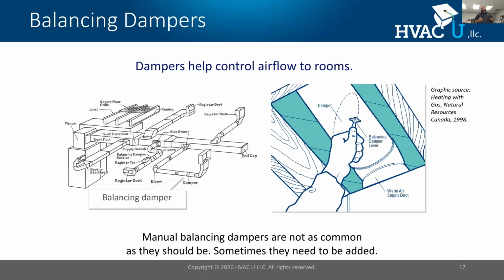Now, in order to balance it, we need balancing dampers. A balancing damper is a piece of metal that goes into our duct distribution system, and typically it goes into the branches. Its purpose is that oftentimes there is a difference in CFM requirement between heating and cooling. In Michigan, where I'm located, we are predominantly heating, and we have a different BTU requirement for cooling. So those airflows are often mismatched. The way you size duct systems, you have to size it for the worst case. And when we size it for the worst case, we have to use a damper to correct the airflow for the other case.